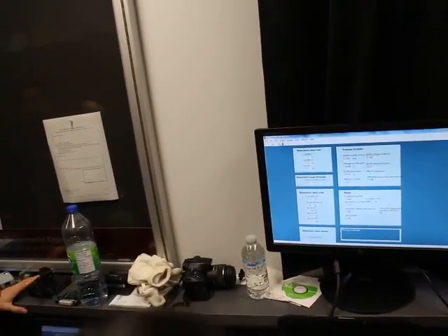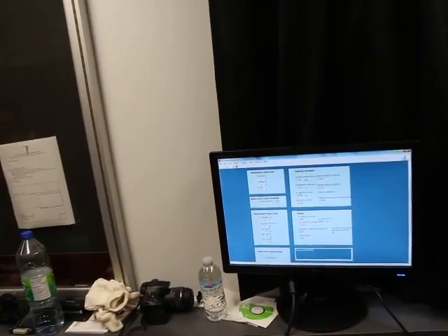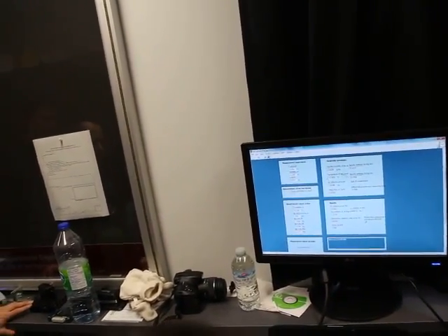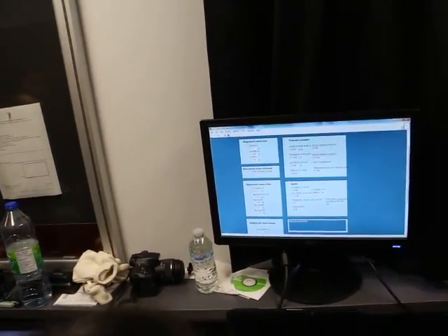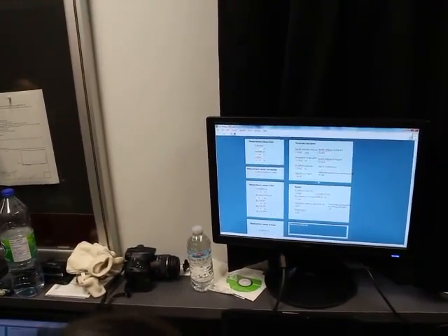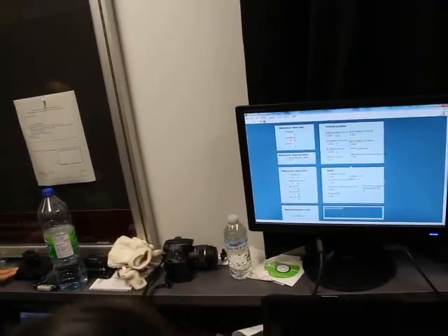It takes into account the mass flow and differential pressure. The volume flow is measured according to the ISO 5167. It's also checking if the dew point is reached, because the values would not be valid if we are below the dew point. So it's always also checking if we have the dew point, and then it's calculating the specific enthalpy at the entrance and the outlet. So it takes into account the humidity too. The humidity content, sure. That's a water content calculation.